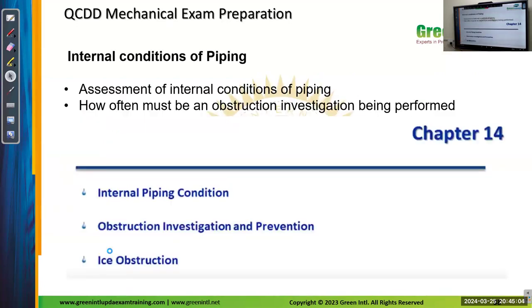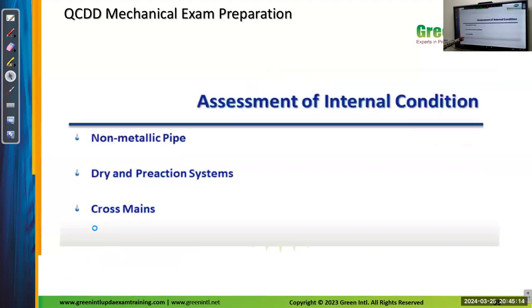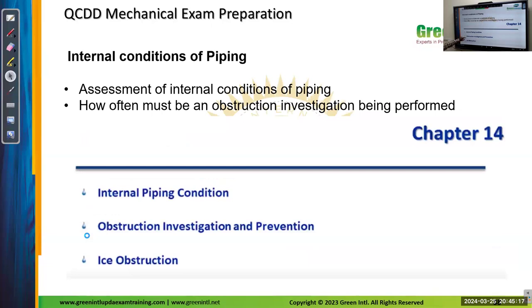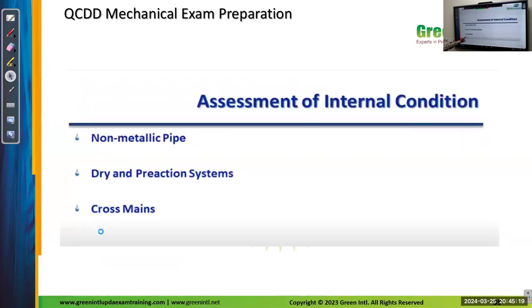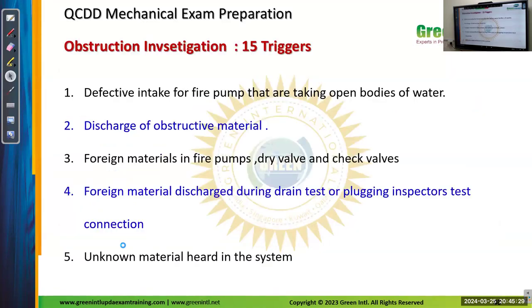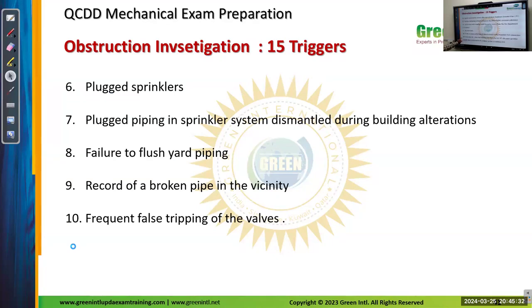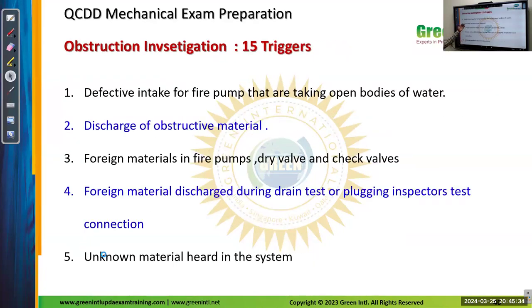Internal conditions of piping. Assessment of internal conditions of piping. How often an obstruction investigation is performed. So internal piping conditions, this is mainly for areas where cold temperature is there, whether it is ice or water. So assessment of internal conditions covers non-metallic pipe, dry pipe systems, and cross lines. Obstruction investigation. There are 15 checklist items. We have to find whether there is any obstruction in the main water supply or not.